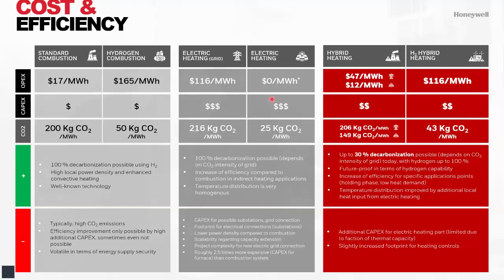Yes, it is more expensive than a standard combustion solution, and I'm going to show you a calculation in a couple of slides. And yes, we need a bit more footprint in terms of controls. Your control system is not only a simple burner control now, like a 7800 or a SLATE. The panel we need is slightly larger, and we need to put the power electronics somewhere, but typically it's acceptable.